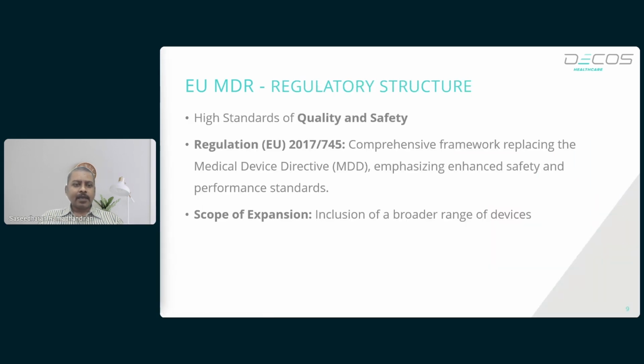Just like with the FDA, the EU MDR has its own regulatory structure that is designed to ensure high standards of quality and safety for medical devices. Let's explore the key components of this structure. The EU MDR came into force in May 2021, replacing the Medical Device Directive (MDD). The EU MDR introduces a comprehensive regulatory framework that raises the bar for safety, performance, and post-market monitoring of medical devices. EU MDR applies to a wide range of medical devices, from simple bandages to complex implants.